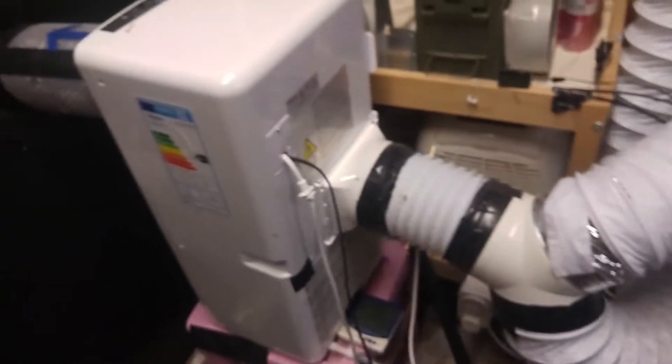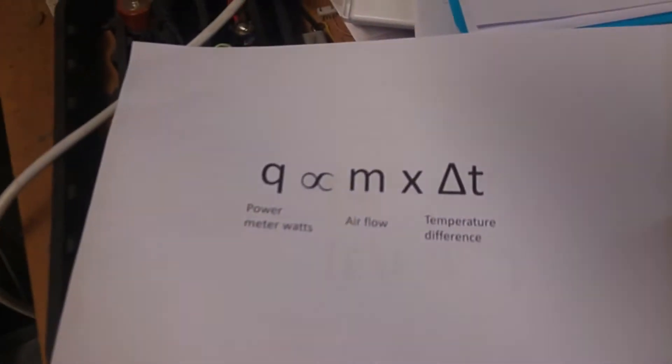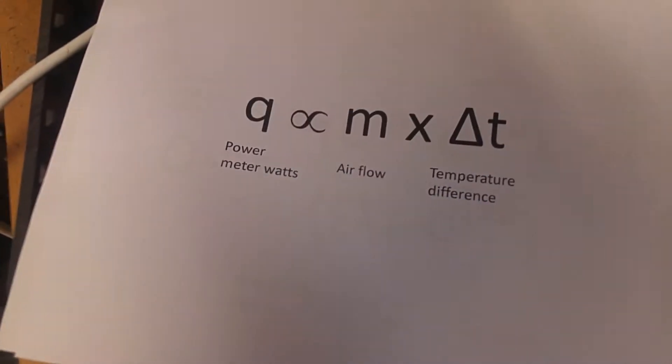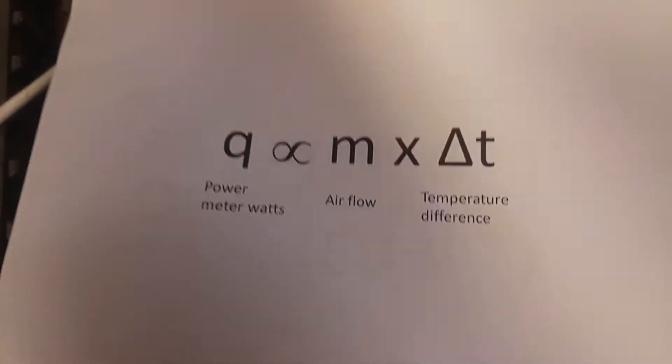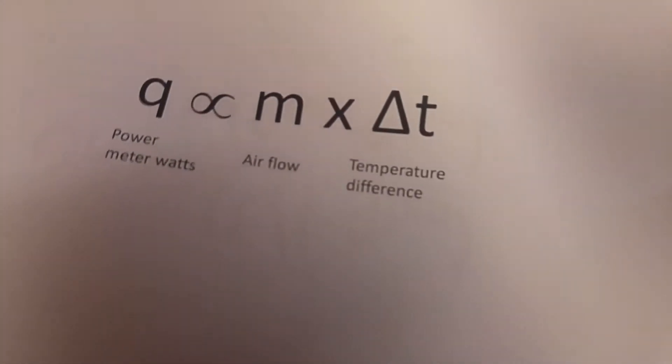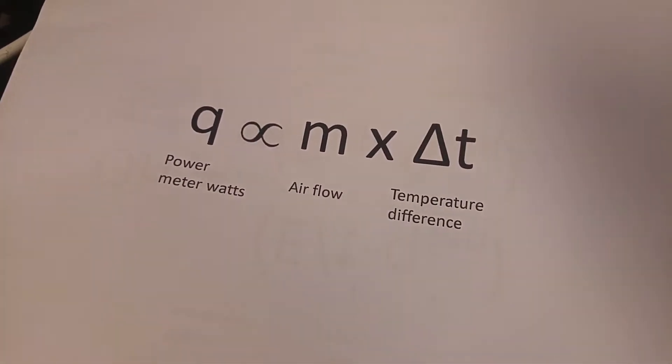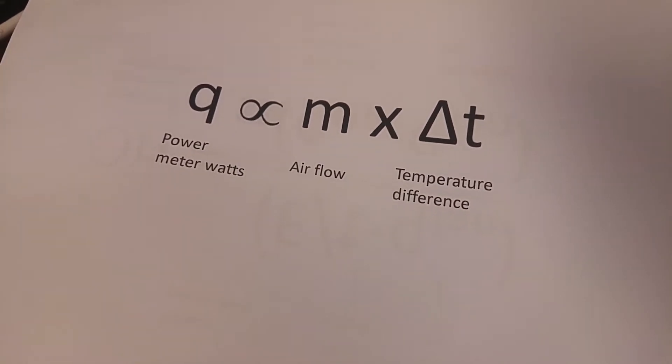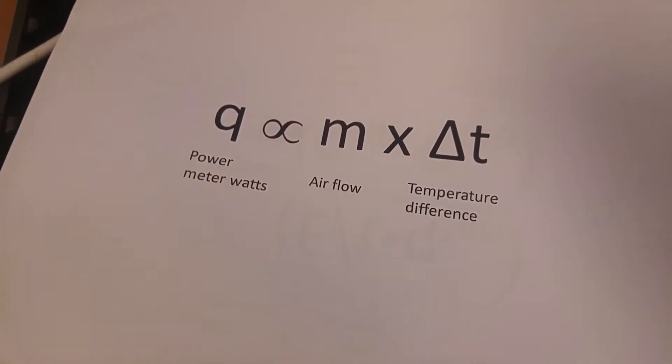Okay. So then you just run the equation backwards to find M, the air flow. Q is the power meter reading, which is from there. And delta T is the difference between the two thermometers. You have to wait five minutes for the reading to get steady state. So let's do that now.